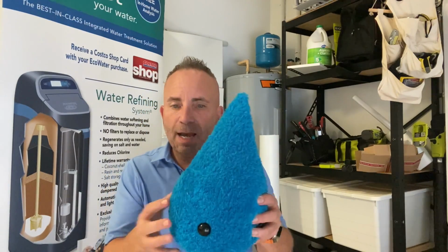All of a sudden, you hear it pop. Have you ever noticed that? Some old water heaters, they're going pop, and people go, what is that? Well, it's the rock, and what's happening is it's cracking that rock, or it's popping it, letting air out. Pop, pop. So that means you're loaded with rock down there. What it means is you're spending a huge amount of money on natural gas to heat that. So that popping is actually the fact that you never address the rock in the water.